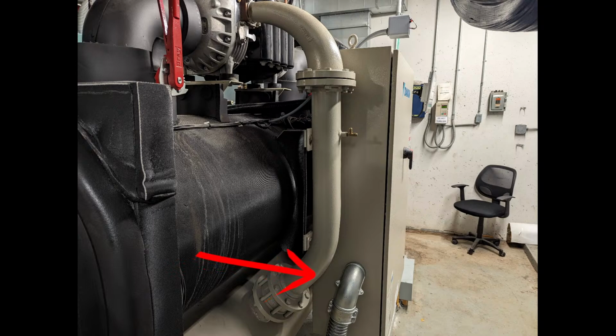Jason, I do see your comment. At the moment it would take a second for me to boot one up, but I can throw that picture into the later video of this. So either way, once we're spinning and we're at speed, this check valve just stays open from there. A huge part of what happens, though, is during the startup cycle, as the compressor is starting to build some pressure on the discharge, it'll build enough pressure to momentarily open the check without actually being able to sustain it.